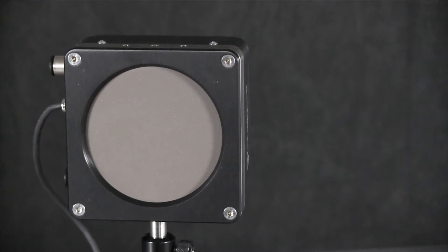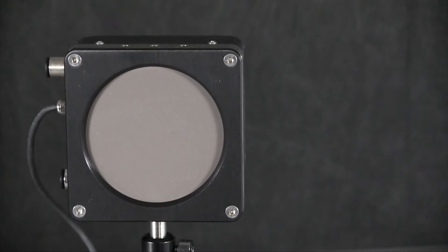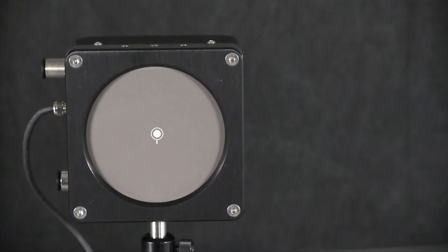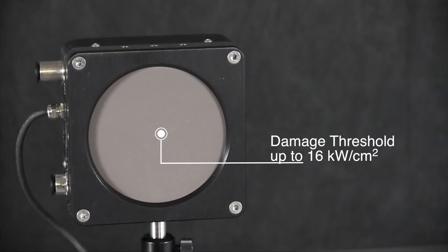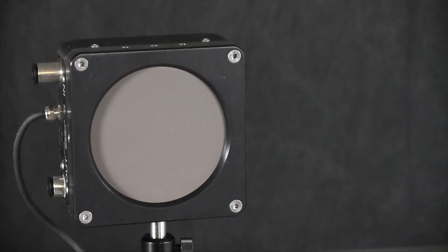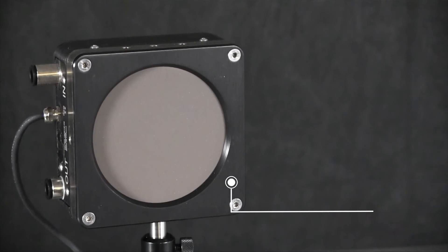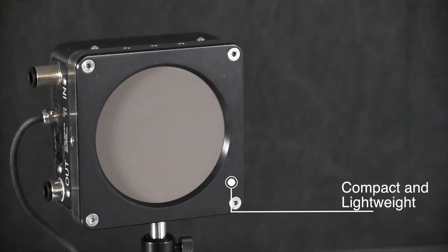Now let's take a close look at the typical features of our HP laser power probes. The front surface is a high absorbance coating with a damage threshold of up to 16kW per square centimeter. The overall package is compact and relatively lightweight.